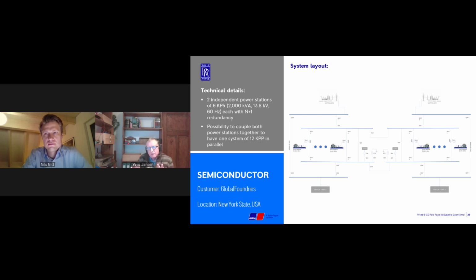And what we have done in addition, as we have 2 power stations of 6 no-breaks working in N+1 configuration, is that we have the possibility to couple those 2 independent power stations in order to have 1 power station of 12 dynamic UPS working in parallel. The main purpose of this is to be able to keep the N+1 redundancy even if we have stopped 1 machine on 1 of the power stations. So we keep the N+1 redundancy by coupling the 2 power stations of 6 no-breaks in order to have a power station of 12 no-breaks, or 12 MTU kinetic power packs.